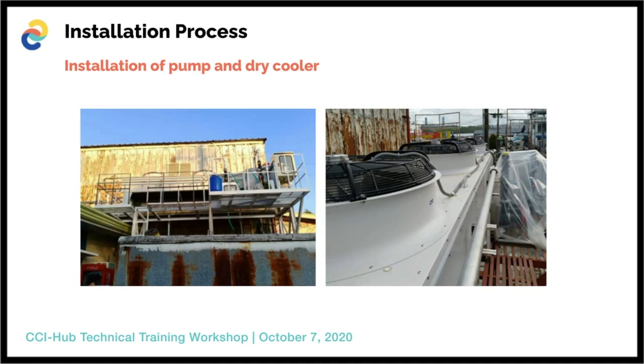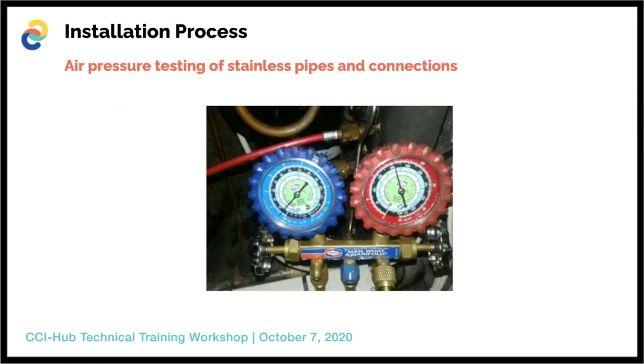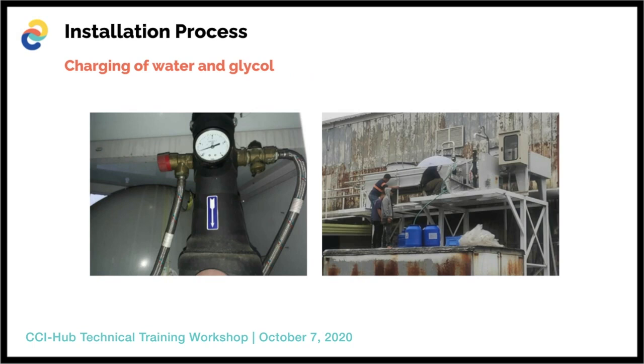Air pressure testing of stainless pipes and connections. By doing this procedure, we'll make sure that there will be no leaks in the systems. We will be using oxygen-free dry nitrogen to double check all piping connections for possible leakage. And the next one is charging of water and glycol.